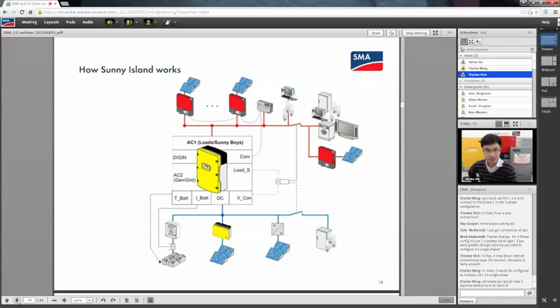You can use our Sunny Island Charger 50 or any third-party DC to DC chargers. Whenever you have third-party DC chargers or loads, remember to add the shunt on the negative side of the battery, so the Sunny Island can tell how much is charged and discharged on the DC side. Everything that goes through the Sunny Island it can tell, but things on the DC side it can't. If you don't have the shunt, you'll most likely overcharge the battery, and good luck - the battery is quite expensive.